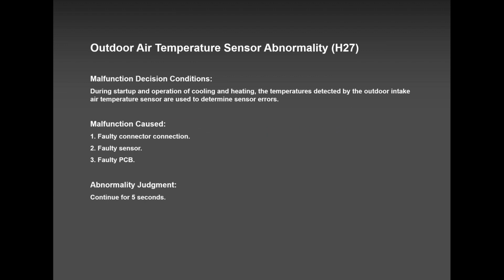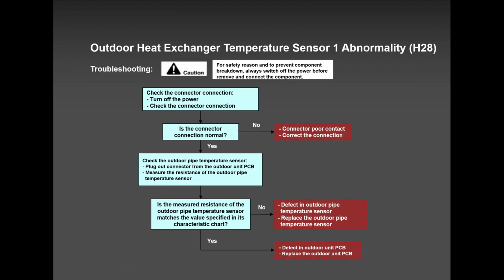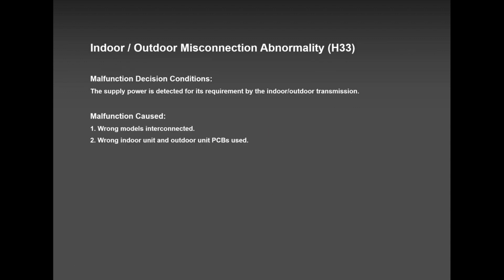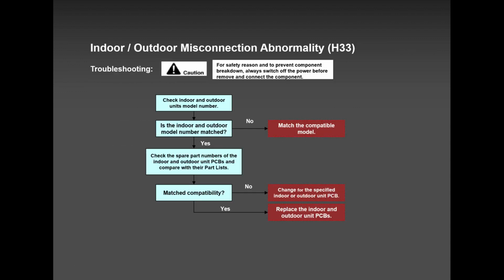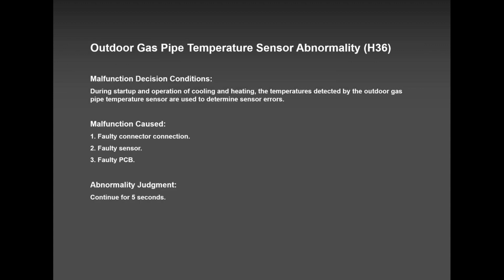H27, outdoor sensor. This can happen if snow got piled up so much on the unit, and now it's throwing all the wrong readings. So now the sensor is picking up all snow temperatures, ice temperatures. So make sure you go outside, you clean everything, and you should be good. H28, very rare, but it can happen. H33, my experience is low voltage. Low voltage caused H33. So make sure your voltage is good, guys.